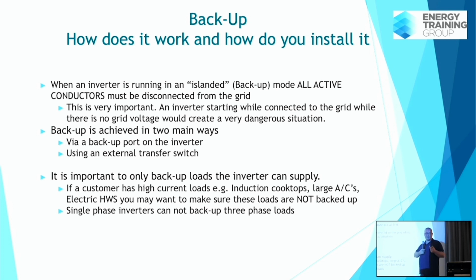So it's important that backup's probably the most complicated part of installing batteries. So you need to understand how to install it. The most important thing about installing a backup system is that when you are in backup mode, all active conductors must be disconnected from the grid, right? We should all be familiar with anti-islanding from a PV system.